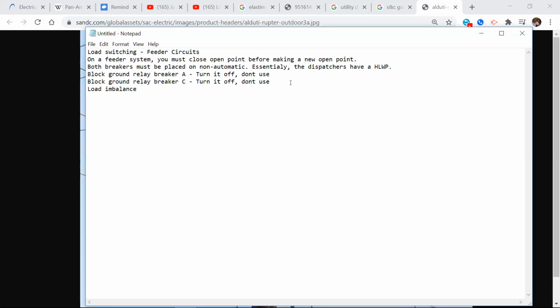Load imbalance, remember? This actually even happens in secondary too, when you don't have one phase of secondary that has the correct amount of load on it. What conductor takes that load imbalance? If you have load imbalance on a circuit, it flows on which conductor? You guys are slow today. Neutral. Yeah, there you go. Flows on the neutral. Okay, it's trying to shed that load that's imbalanced to the neutral, and the neutral is grounded, correct? Yep, the neutral is grounded.